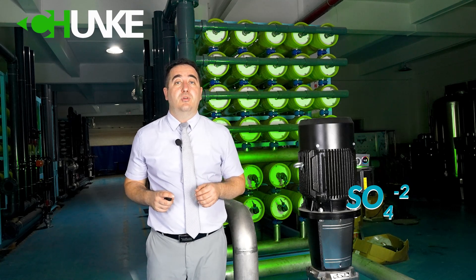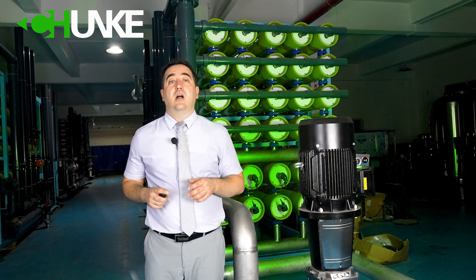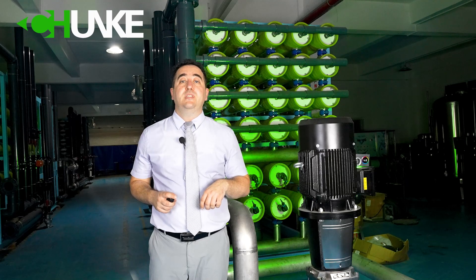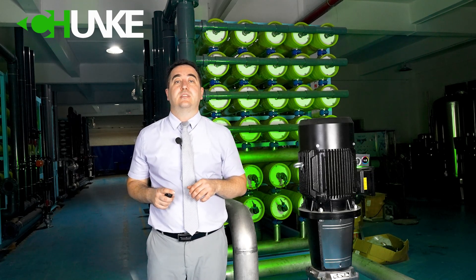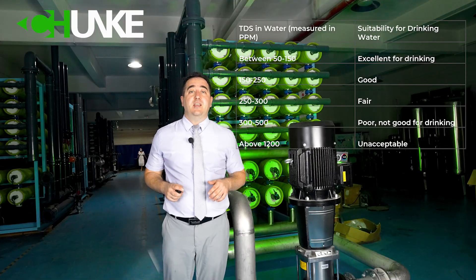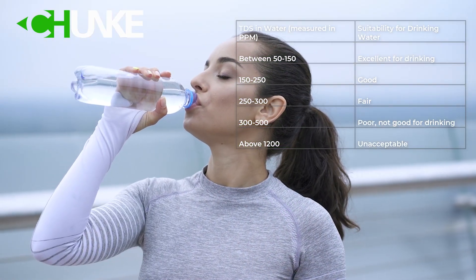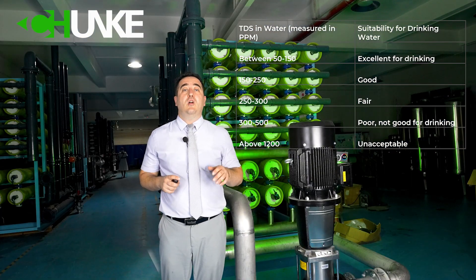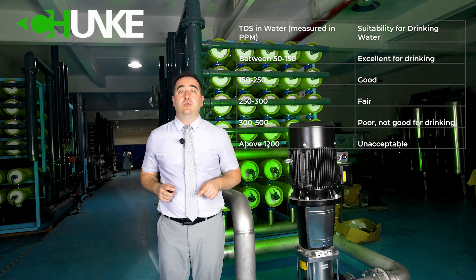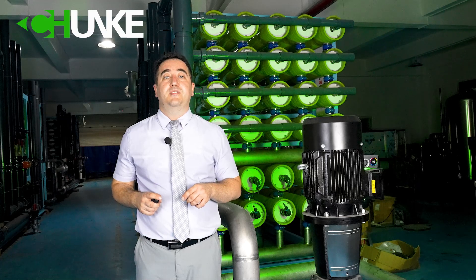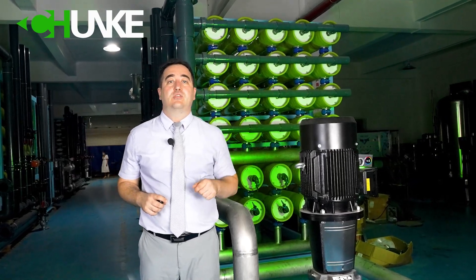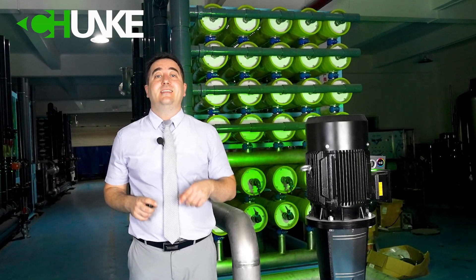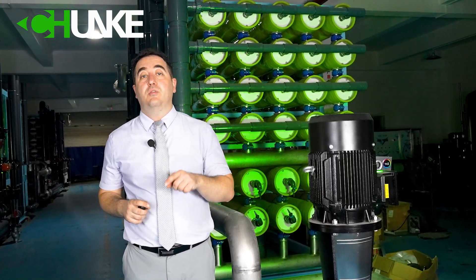Why is TDS important? We categorize water according to its TDS level. Now I will show you two tables — from these tables you will see this categorization. For drinking purposes, if you want to drink water, TDS level must be less than 250 ppm. If you are producing bottled water, we suggest you produce water less than 150 ppm. Also, if you want to use this water in your process, you have to define the needed treated water TDS level for your process.